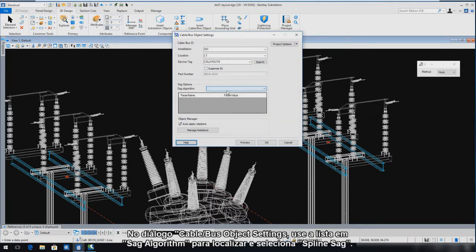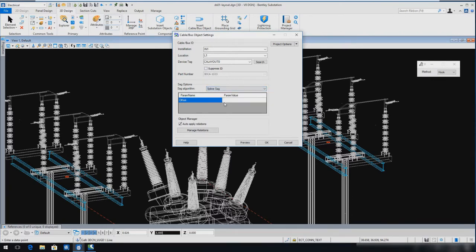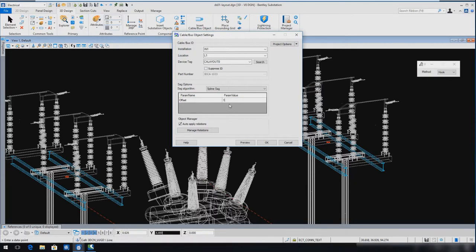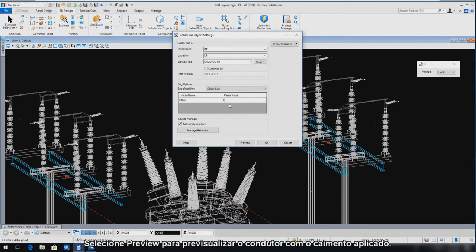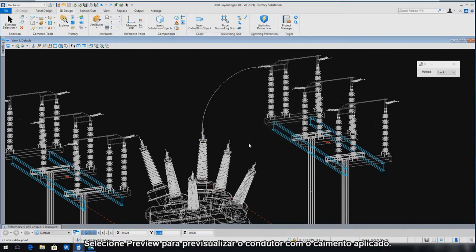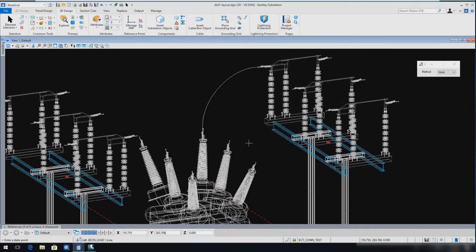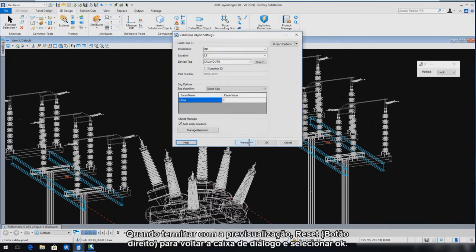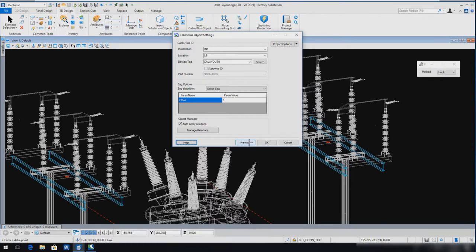In the Cable Bus Object Settings dialog, use the SAG Algorithm drop-down list to locate and select Spline Sag. Double-click the Offset Param Value field and key in a value of 1. Select Preview to see a preview of the conductor with the SAG applied. When you are finished with the preview, reset to return to the Cable Bus Object Settings dialog, then select OK to accept the preview and complete the insertion.